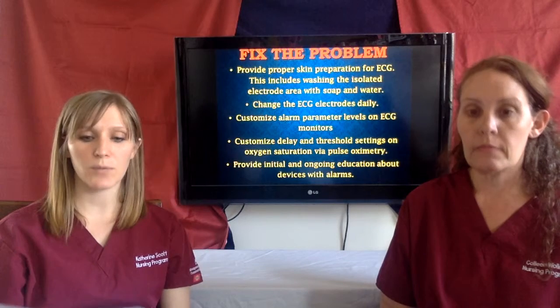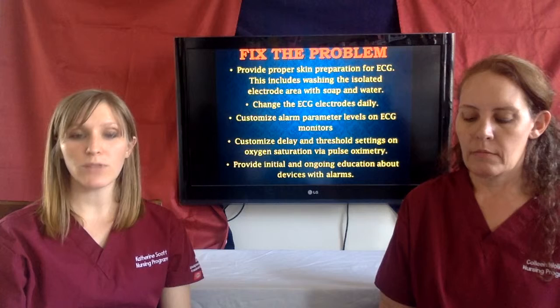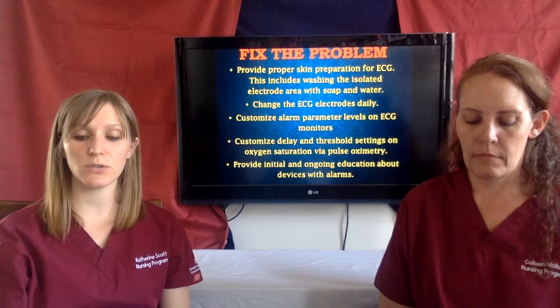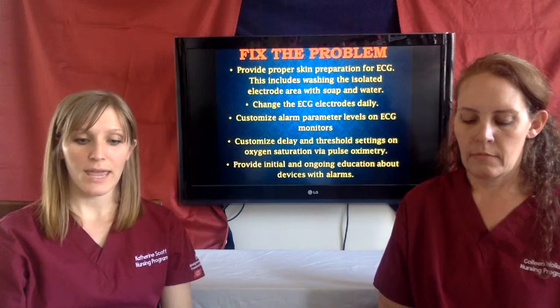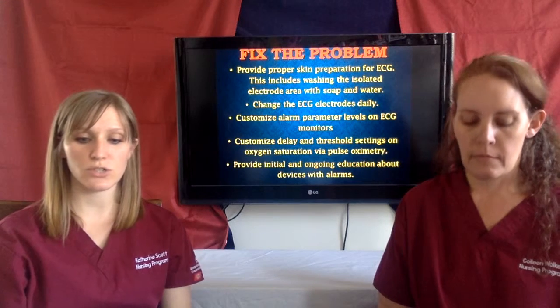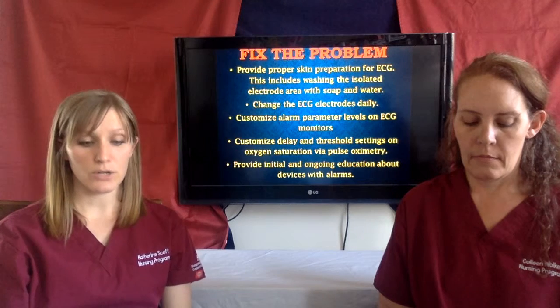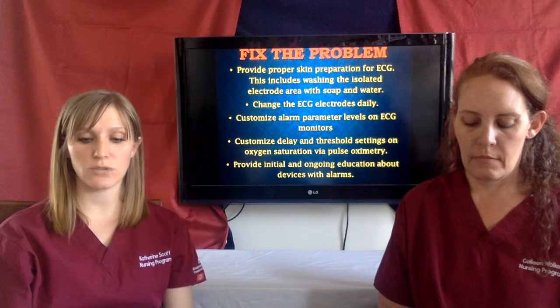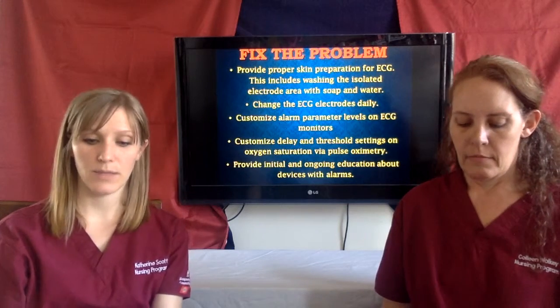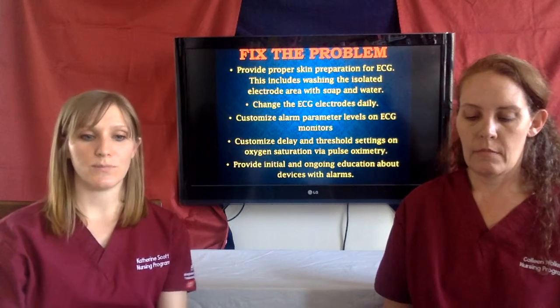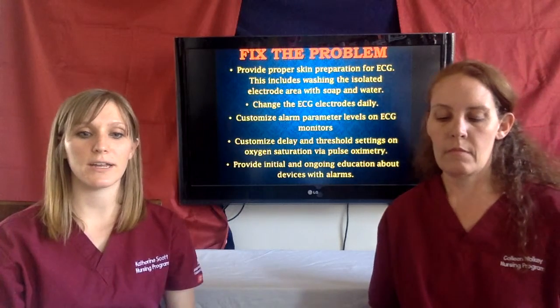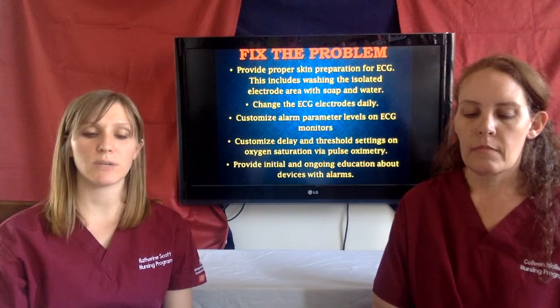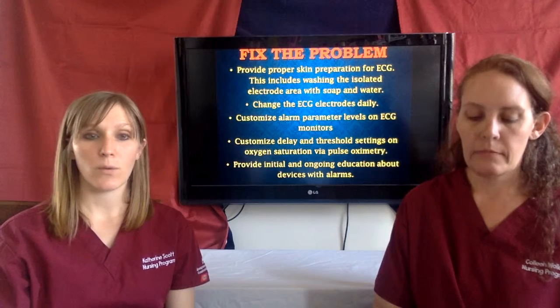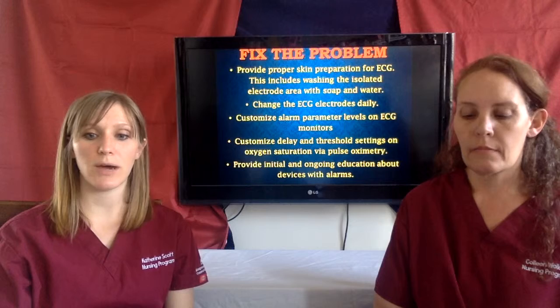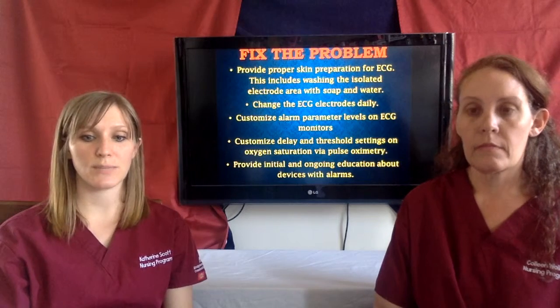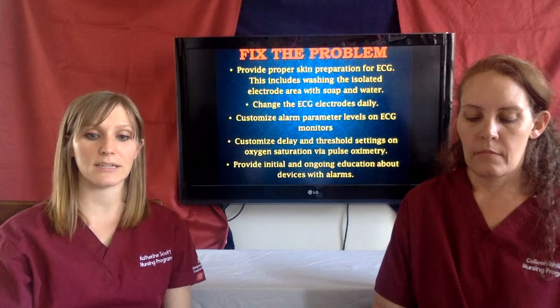You could also customize alarm parameter levels on ECG monitors. A 43% reduction in critical monitor alarms was observed in a critical care setting when default setting parameters were changed, including the customization of the alarms, and registered nurses were educated about the change. You could also customize delay and threshold settings on oxygen saturation via pulse oximeters. Delaying the time from when the event initially occurs to when the alarm is triggered on an SpO2 alarm to 15 seconds can reduce the frequency of alarms by 50 to 70%. Or you could also provide initial and ongoing education about devices with alarms. Develop a safety culture embraced by staff members which promotes identification of factors that may lead to patient harm.